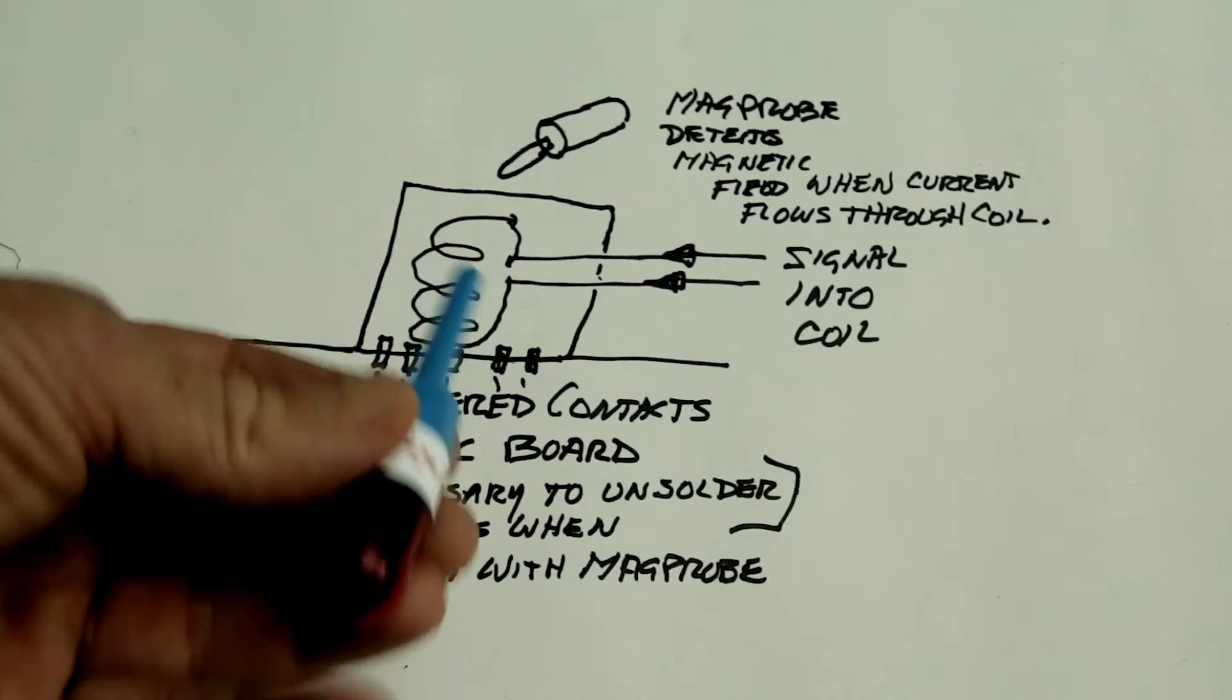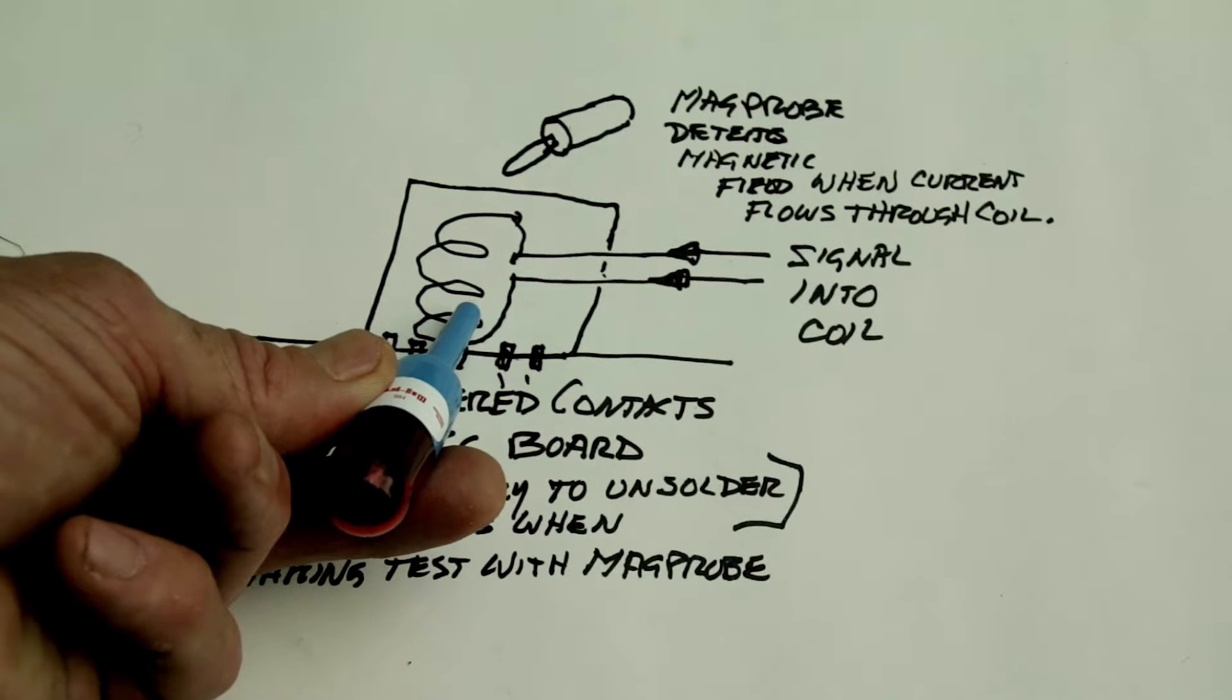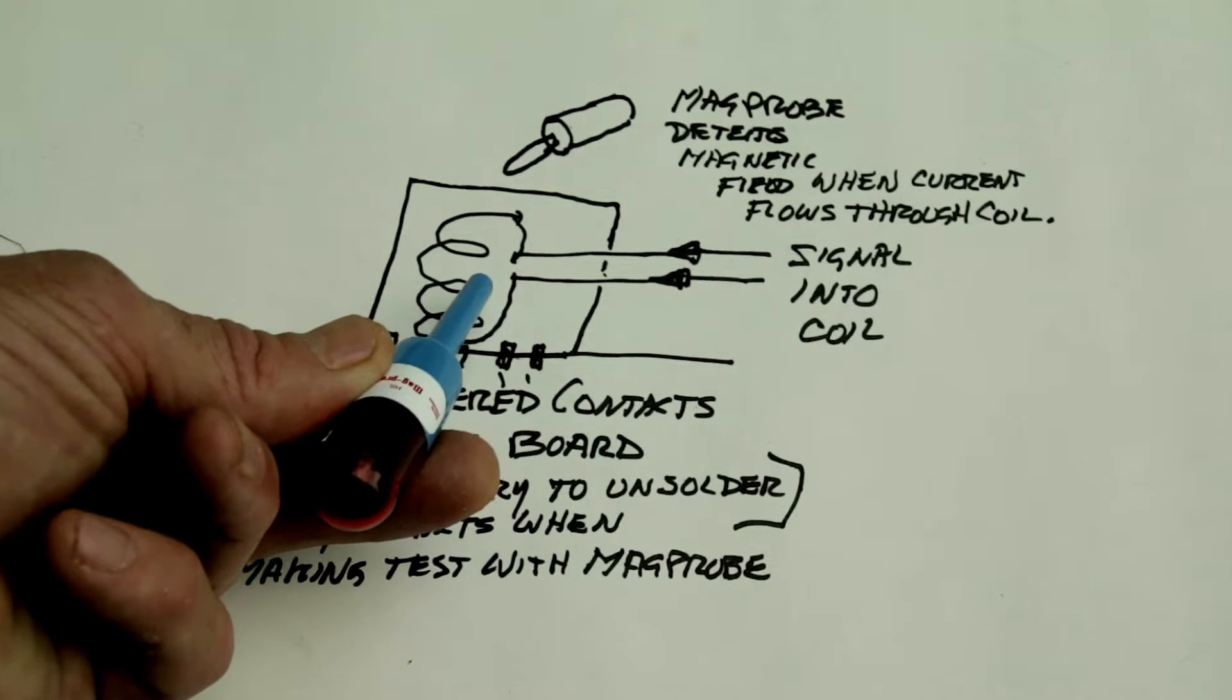If you hold the mag probe up to this coil while the relay is supposed to be energized and there's nothing, that means there's something wrong here. You've got an electrical problem.